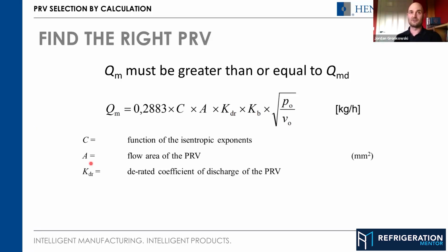And we therefore flow test our valves at the National Board in America, and we get a rated slope, which is, again, one of the terms that we use from the American side. But we can derive KDR from that. So even if you have an American valve that's only certified on slope, you can again derive this KDR term from the slope. KB is what's called the theoretical capacity correction factor for subcritical flow, which is a bit of a mouthful, but effectively that is always 1 if your valve is supersonic internal flow, which all of these refrigerant ports generally are. So you generally don't need to worry about that term too much, unless you have a strange valve.